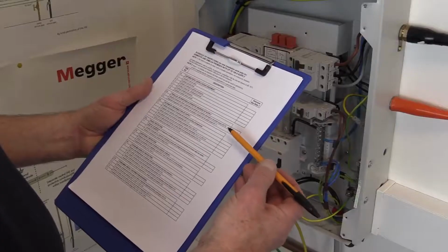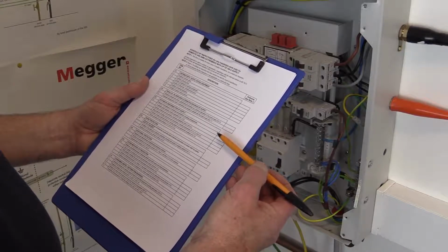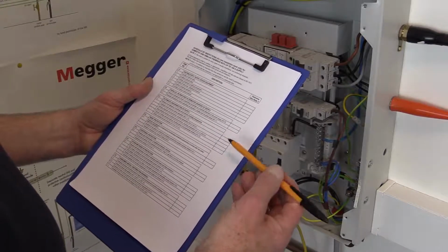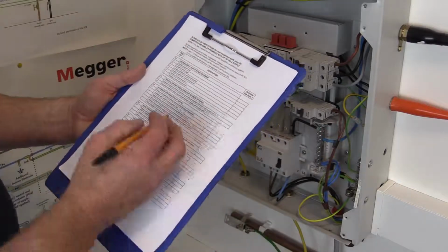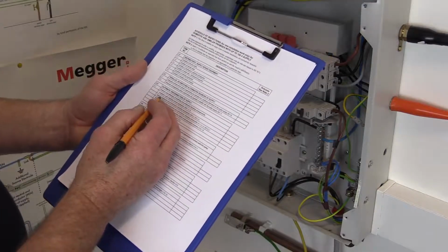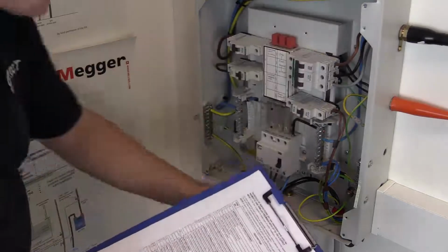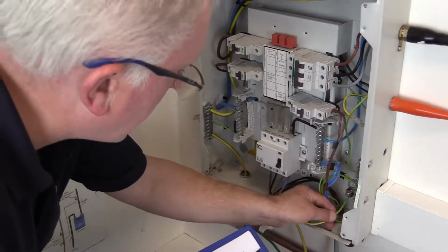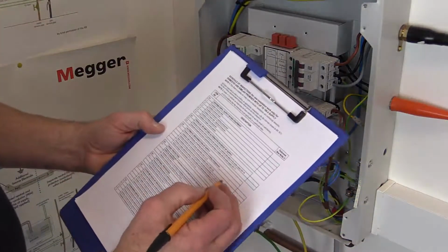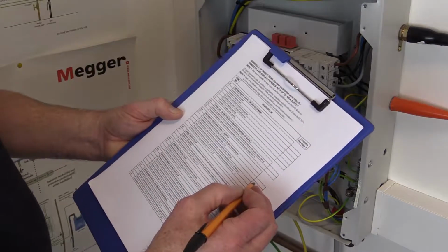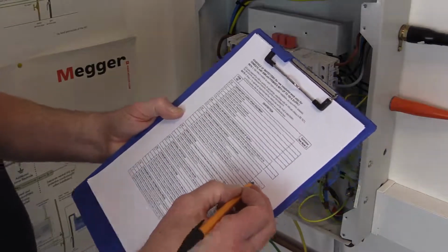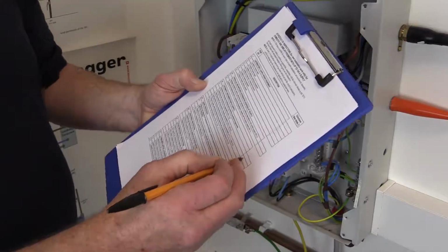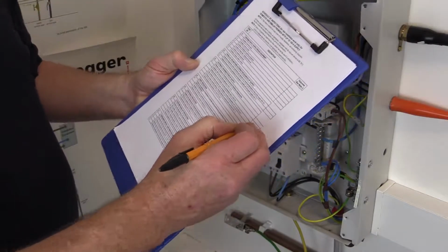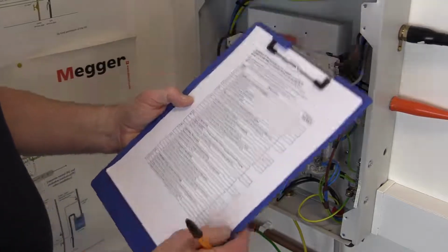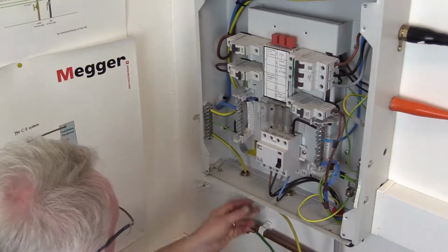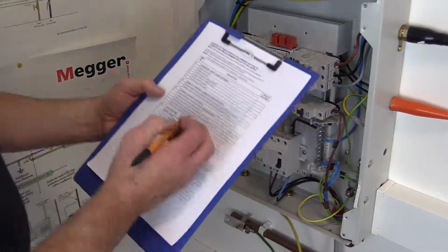The results of the inspection should be recorded on a schedule of inspections, which should be based on the model provided in Appendix 6 of BS 7671. This could be used during the inspection process to remind the inspector of the items that may require inspection. When completing the schedule, the outcome of the inspection of each relevant item should be recorded as satisfactory, and those items not applicable should be identified by inserting an N/A indication in the relevant box.